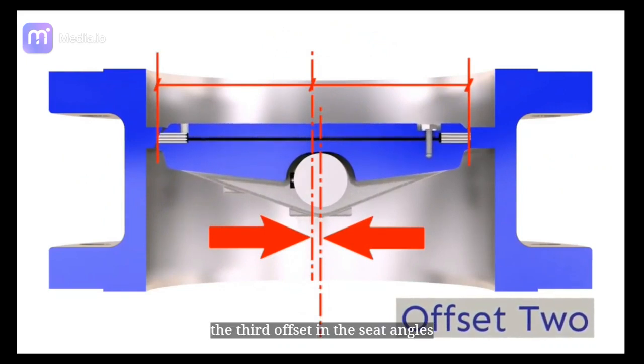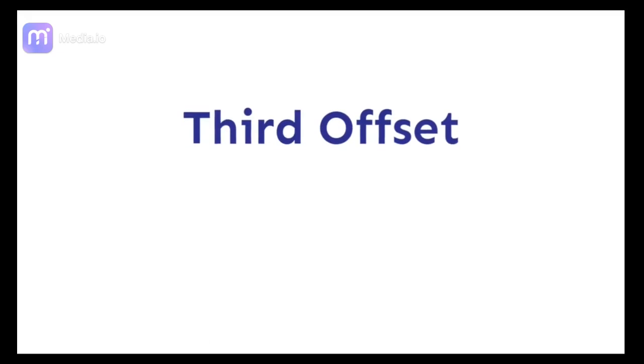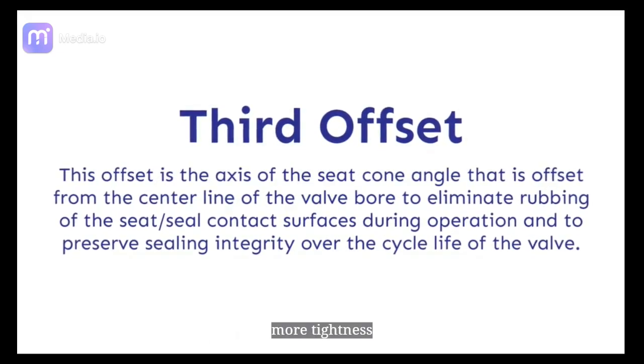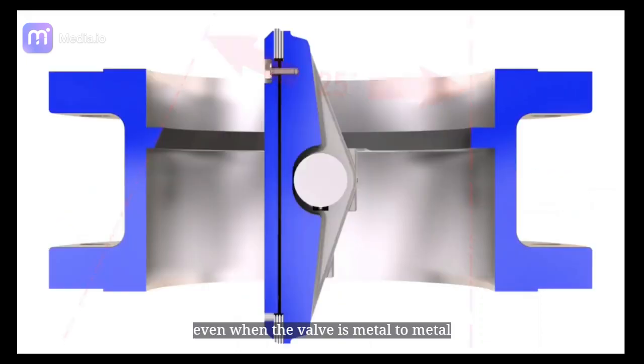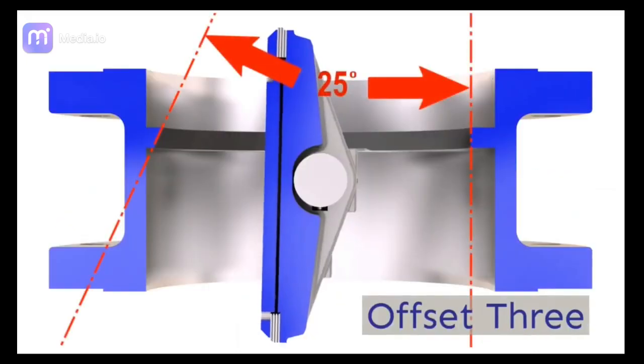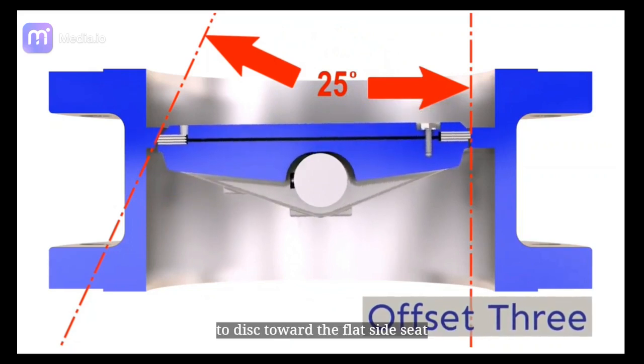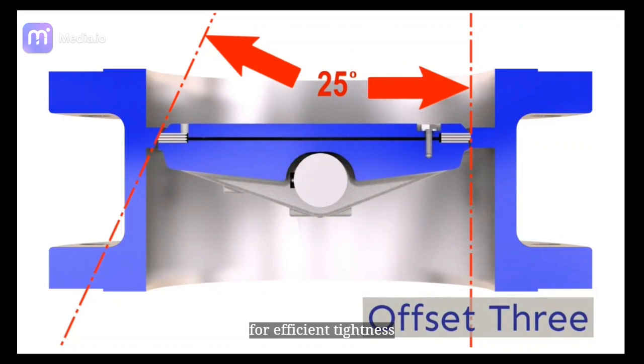The third offset in the seat angles, machined like a unique conical angle, helps for more tightness even when the valve is metal to metal. One side angle seat imposes enough force to disc toward the flat side seat for efficient tightness.